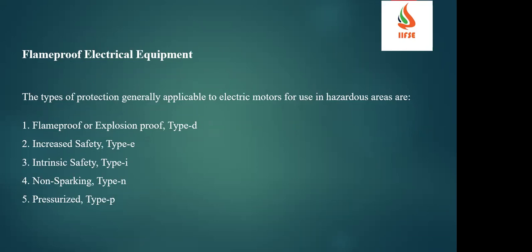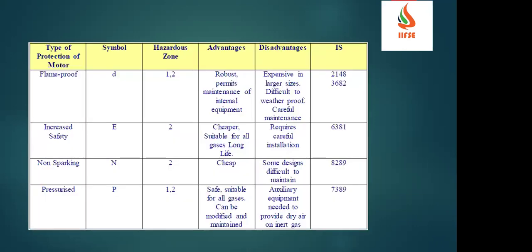Now we'll see what kind of flame-proof electrical equipments there are. These are the different types of electrical equipments we can see. One is flame-proof or explosion-proof, called type D; increased safety, type E; intrinsic safety, type I; non-sparking, type N; and also pressurized, type P. These are the different types of flame-proof electrical equipments which we use in hazardous atmospheres.